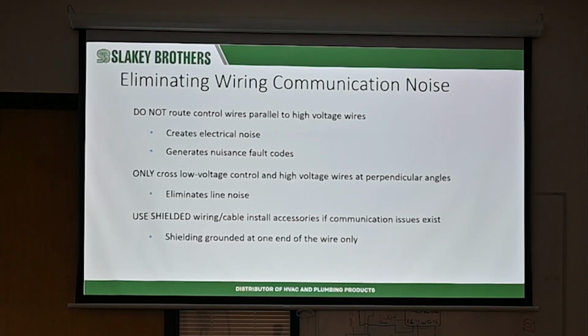Okay, so the basic stuff, wiring. One of the most common things that'll happen in an install is a communication fault. They're like, hey, I'm commissioning my unit, and it's not finding the outdoor unit. It's not finding the indoor unit. I've got a problem. So what we're going to go over is some stuff that's going to help you make sure it doesn't happen.